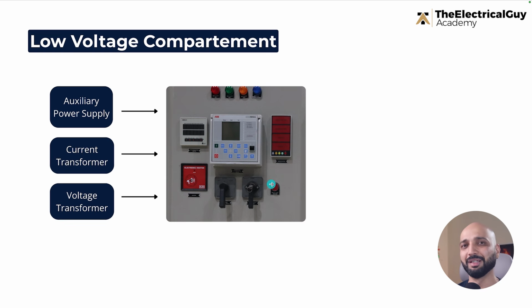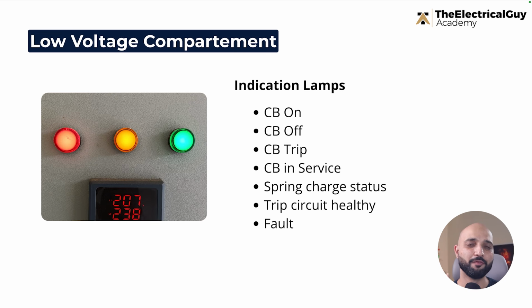Now let us have a look at some of the common things that you will find in the low voltage compartment. The first and most common things are the indication lamps. These are small lamps, but very, very useful to indicate the status of different things. Some examples: circuit breaker on, circuit breaker off, circuit breaker trip, circuit breaker in service. You'll get an indication on top. Spring charge status, of course, for the circuit breaker, whether the spring is charged or not, you will get that indication. Trip circuit healthy, you will get that indication, and maybe even some of the fault indications can be provided with the indication lamps. Please note, this is the list I've mentioned on the screen, but it's not limited to that. These are just examples. There can be a long list of indications, maybe 10, 20 indications on the panel. It's possible. So that's one thing you have to remember. This is not the limitation. These are just a few examples.